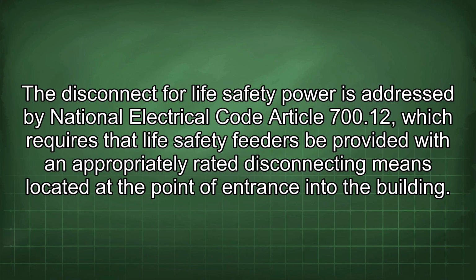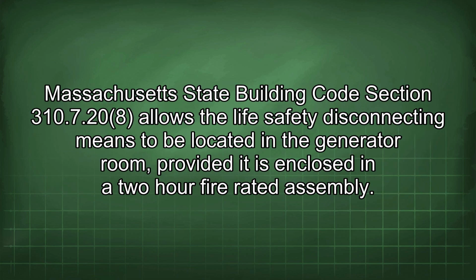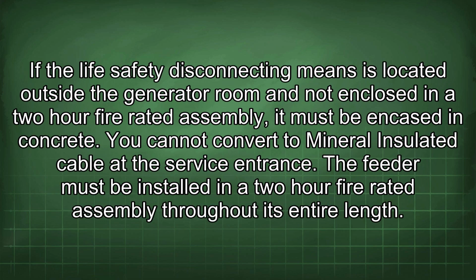The disconnect for life safety power is addressed by National Electrical Code Article 700.12, which requires that life safety feeders be provided with an appropriately rated disconnecting means located at the point of entrance into the building. Massachusetts State Building Code Section 310.7.20(8) allows the life safety disconnecting means to be located in the generator room, provided it is enclosed in a 2-hour fire-rated assembly. If the life safety disconnecting means is located outside the generator room and not enclosed in a 2-hour fire-rated assembly, it must be encased in concrete.